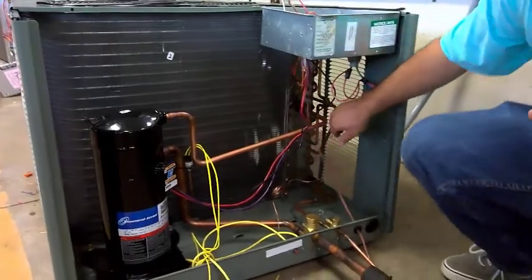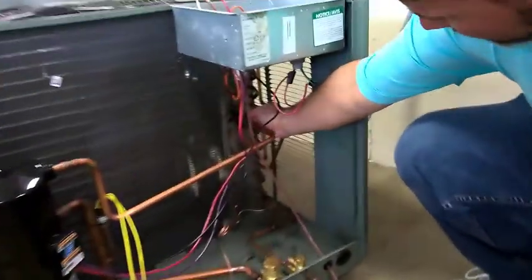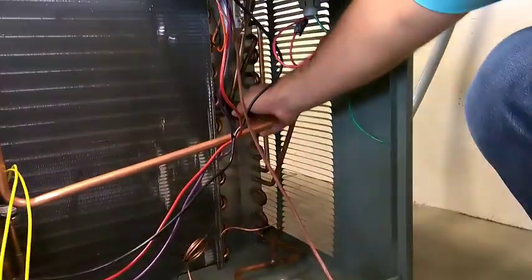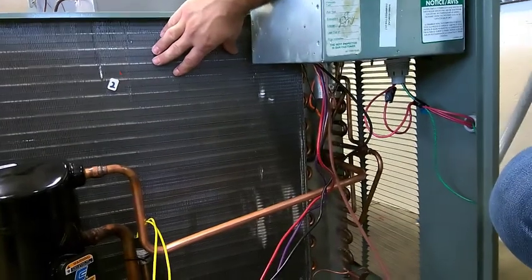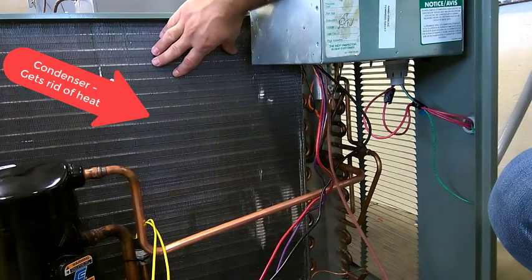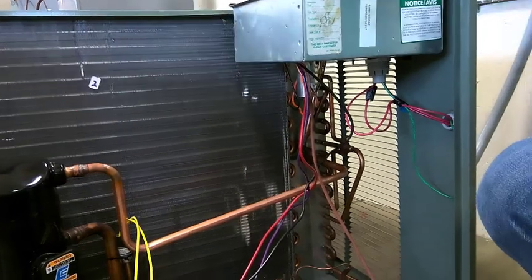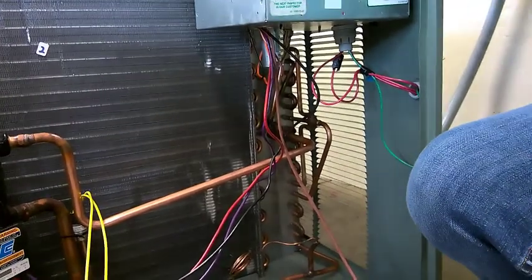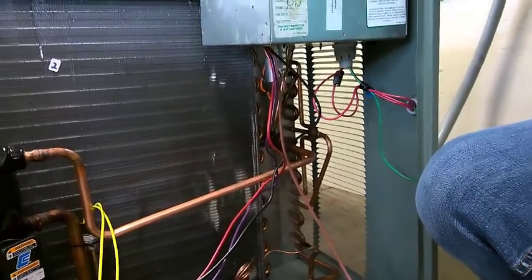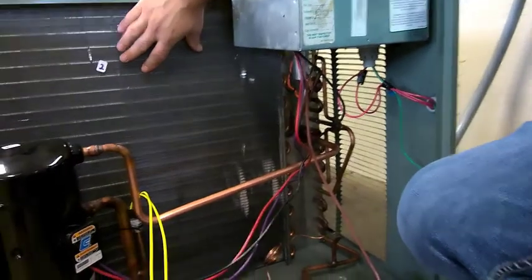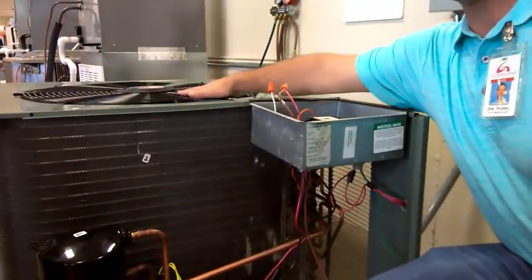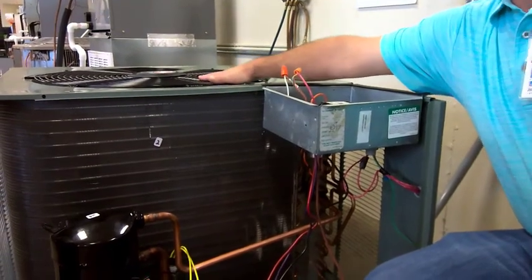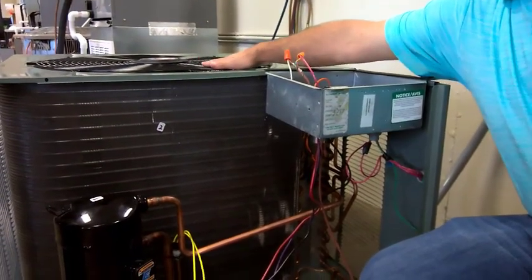If you can get the camera in here, you can see it's going to run to these three small distributor tubes. All that's doing is putting that hot gas inside this condensing coil. As it circulates through there, we blow outside air across it. If I keep that refrigerant at, say, 110 degrees, and I'm blowing 95-degree air across it, I can remove heat from it. I can cool it off, right?